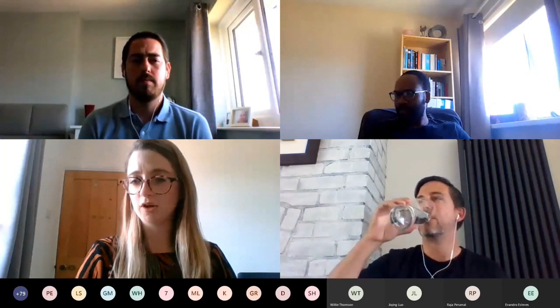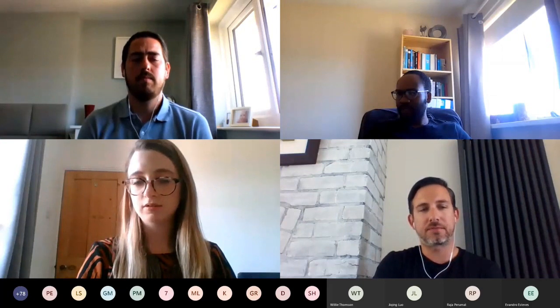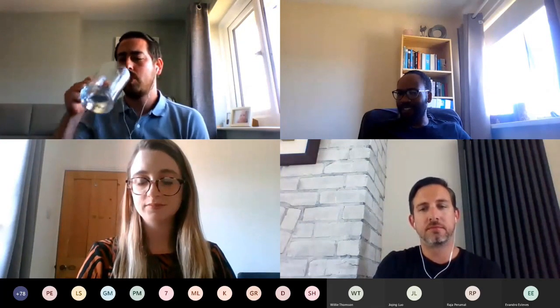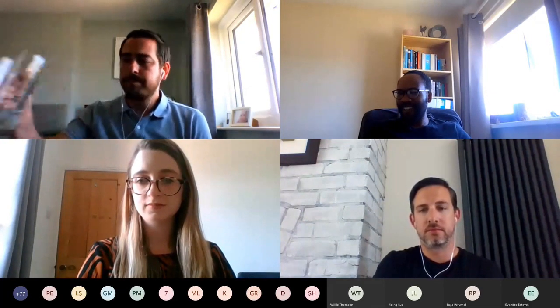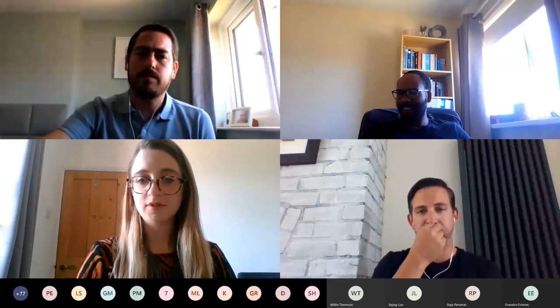So what was the question again? EXI is designed for zone 0. If it is zone 0, you must stop the potential of gas migration through the cable to zone 1 or zone 2. So the EXI gland must seal. So the question is whether the EXI gland must seal? Yeah, this prevents the migration of gas through different zones. So obviously that's something to be aware of when you're selecting your cable gland.